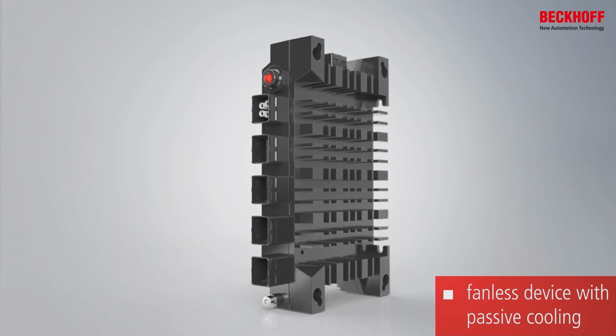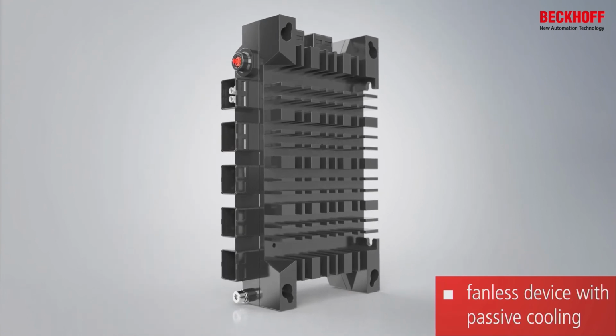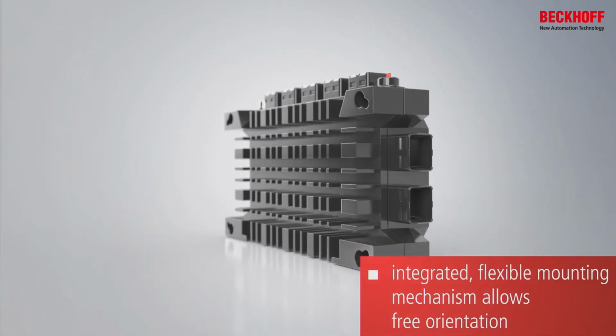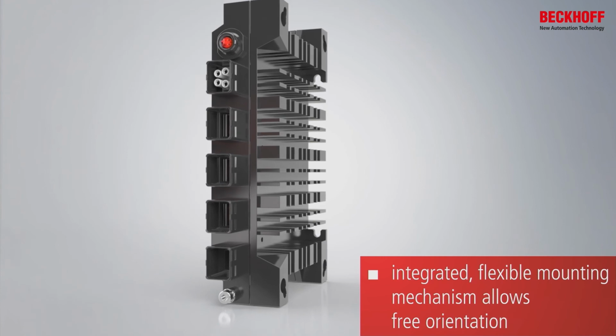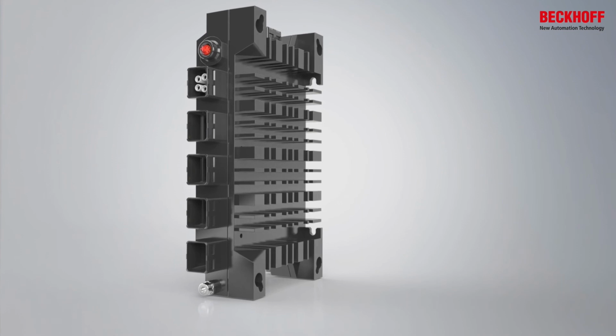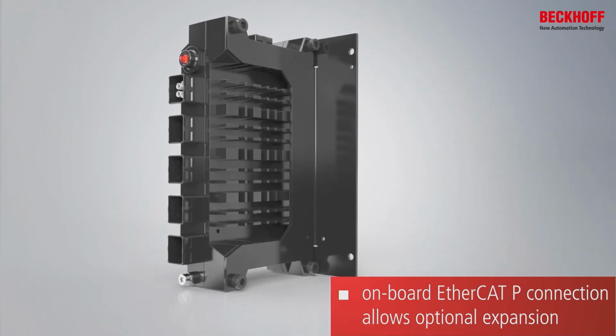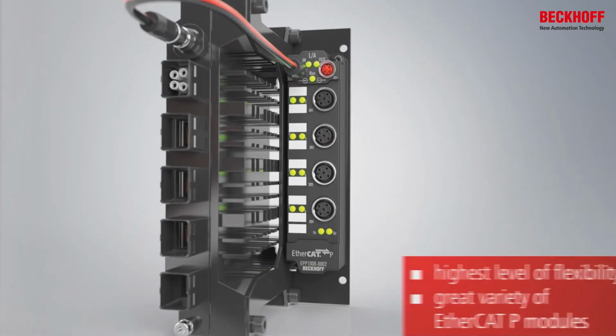With fanless cooling, the C7015 is suitable for a temperature range up to plus 50 degrees Celsius. The device is highly flexible regarding its installation options. The ultra-compact industrial PC is designed for direct mounting on a machine and can be installed on the side or rear panel of the housing due to several integrated fixing points. In any mounting position, space requirements are minimal. The onboard EtherCAT P interface can be extended with numerous EtherCAT P modules as required, allowing users to implement distributed solutions for complex diagnostics or condition monitoring tasks, for example.